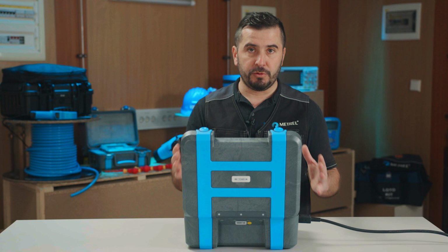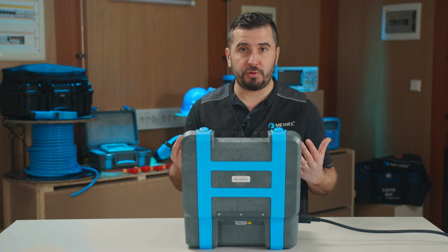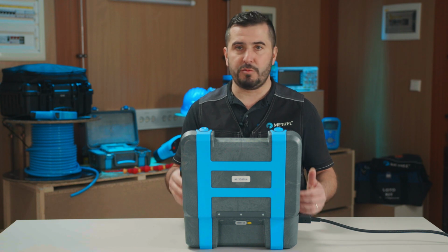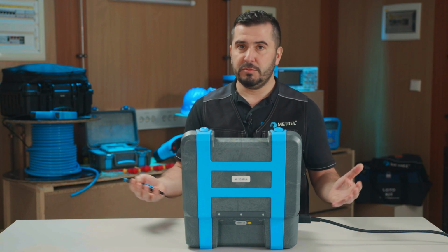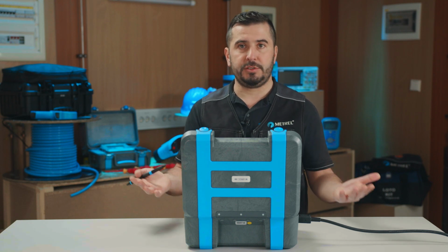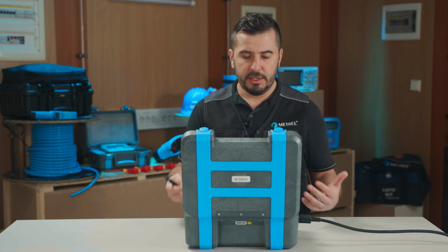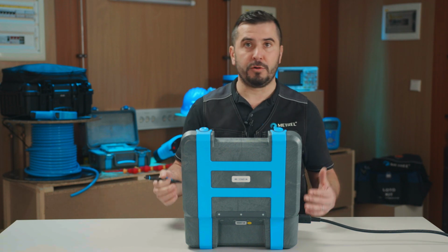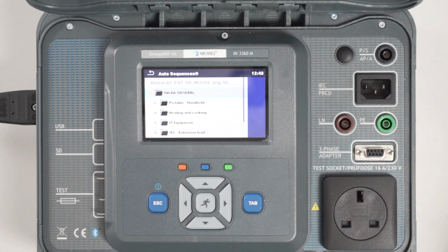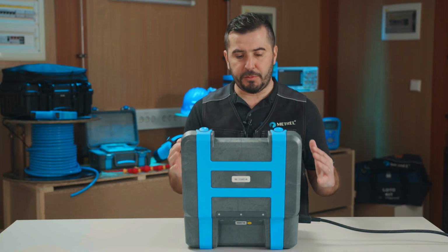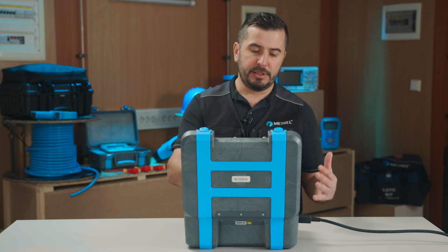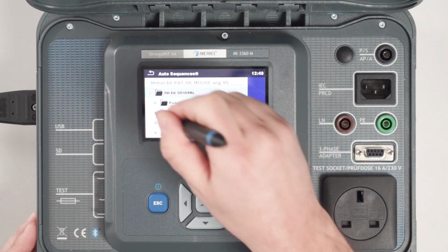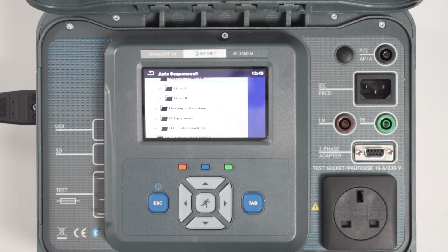What is also a very good feature about these auto sequences is that they can be pre-programmed or modified within the PC software. So if you don't like something about these auto sequences, you can simply download them into the PC software and modify them per your wishes. For the UK market, we have here 3 different groups. We have the group General, where we can find all sorts of pre-programmed auto sequences which are divided into special groups, for example portable handheld, and inside here we see auto sequences for class 1 or class 2 appliances.